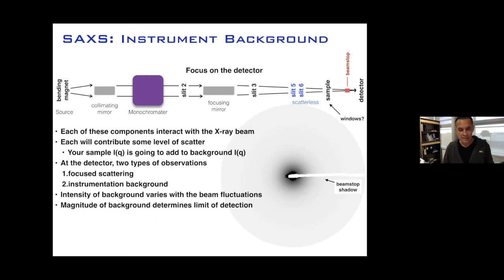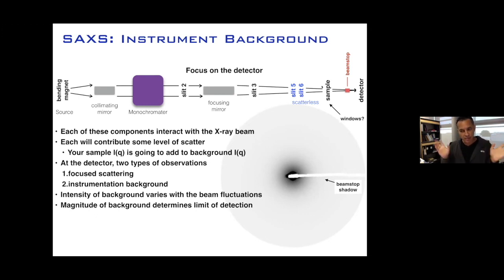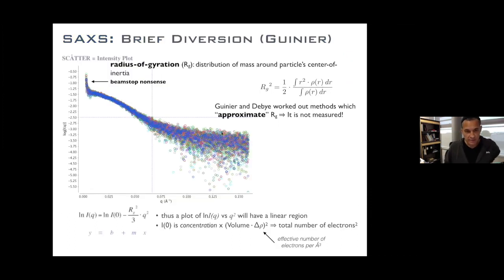The kinds of noise you'll see in your scattering include scattering off slits, mirrors adding background noise, and all the stuff inside the instrument that x-rays interact with contributing to instrumentation scattering. We remove these contributions through the difference measurement, given that everything remains the same. This might become an issue at very short exposures like 10 microseconds, but normally you're in the hundreds of millisecond exposure time range.